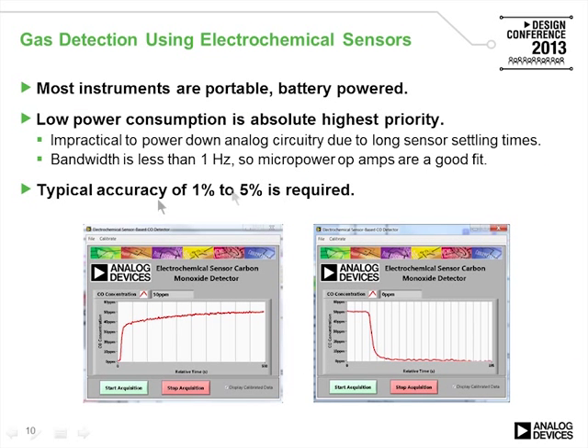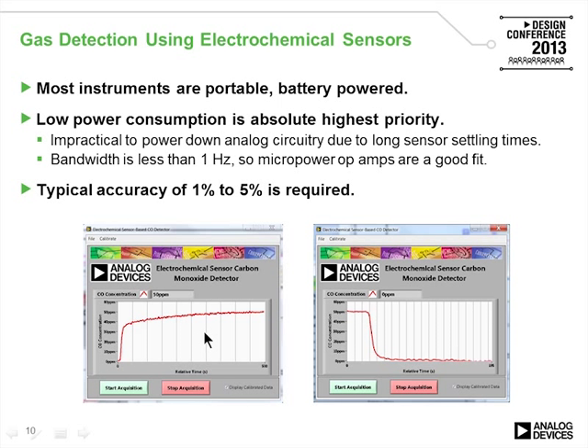This shows the response time when the sensor is first exposed to the toxic gas — in this case, carbon monoxide. The time axis is in seconds, around 500 seconds, so you can see that the response time is pretty slow. An accuracy of 1 to 5% is really about all that's required in these applications.